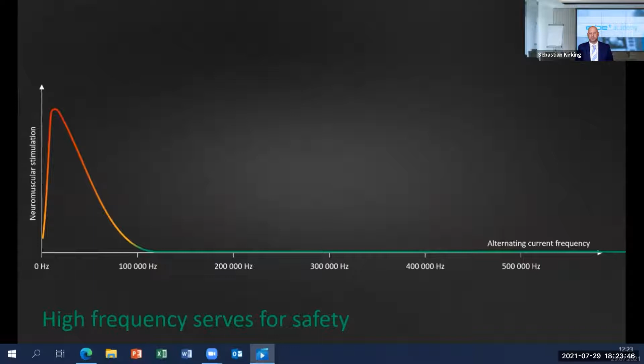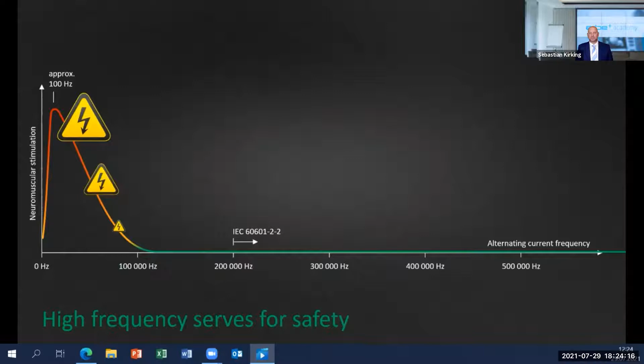With much higher frequency, the intensity of the neuromuscular stimulation becomes weaker, because with higher frequency, the cycles of the alternating current become so short that our nervous system cannot sense the current anymore. By standard, the used frequency must be at least 200,000 hertz or higher for patient safety. The frequency itself has almost no impact on the tissue effect. The type and intensity of the tissue effect is controlled by the selectable settings.